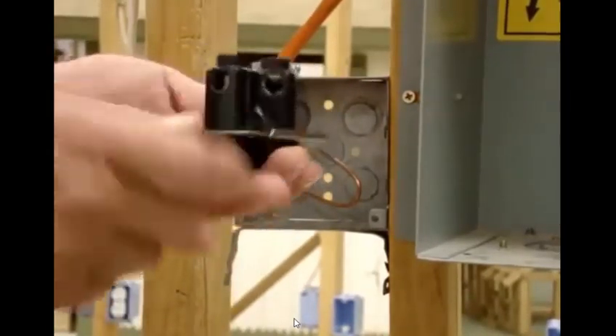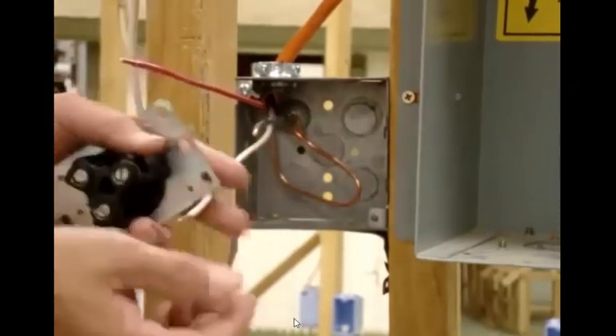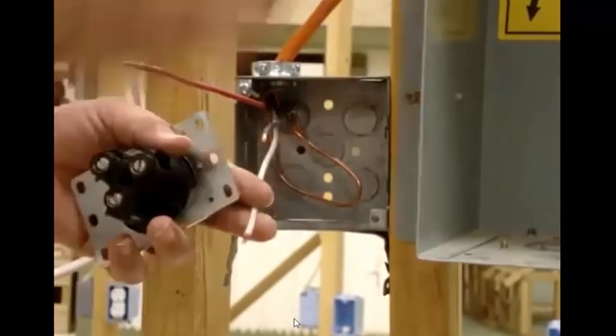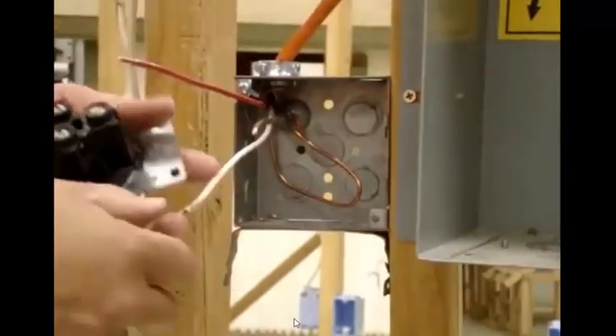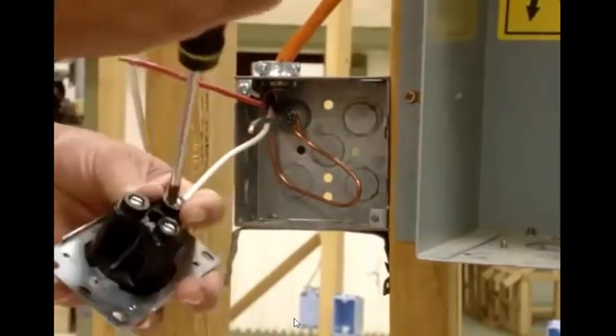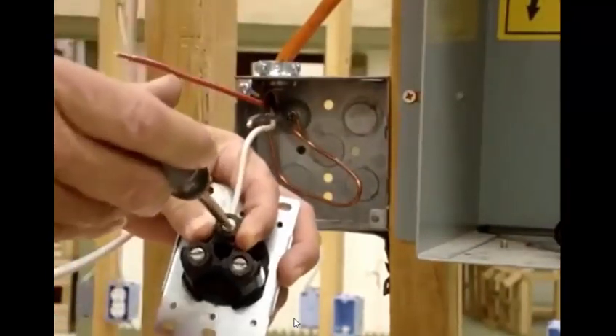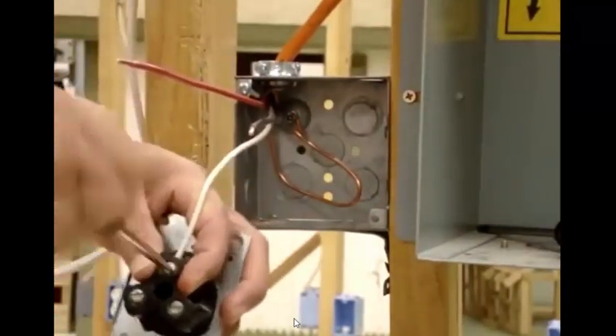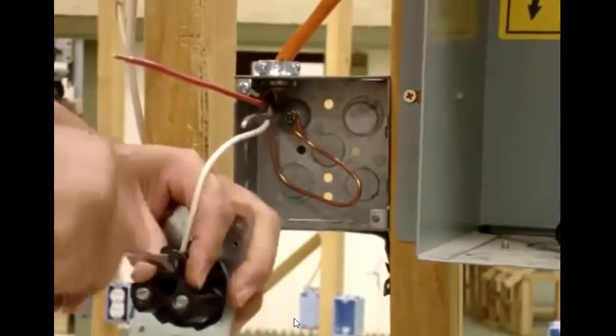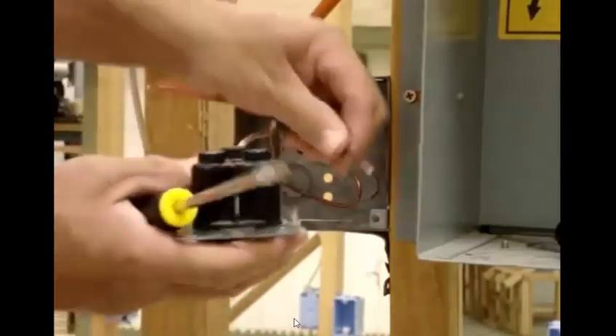We hook it up in the back right here, put it in, and tighten it down. I peeled my wires already. Peel your wires. Put my neutral back here and crank it down. Peel off only about a half an inch — that's pretty good right there — and then start doing the other ones.